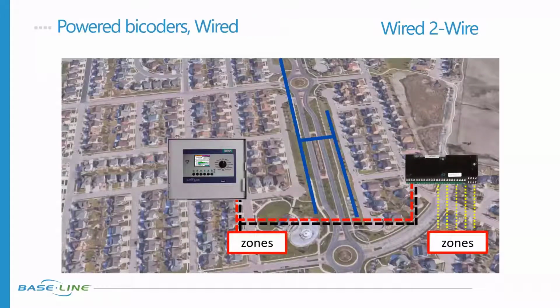So I'd be remiss if I didn't talk about wired 2-wire. Powered bicoders are part of this problem-solving toolbox that we have here. In this case, a powered bicoder is where we have a base station 3200 or a base station 1000, and either controller will work with this, where the substation is an extension of the base station 3200, not the base station 1000. Here I've got a base station 1000 or 3200 connected to a 2-wire path with zones attached to it. Somewhere on that wire path, I've got a powered bicoder connected that's receiving that 2-wire path, and it can run conventional zones or other devices out there.